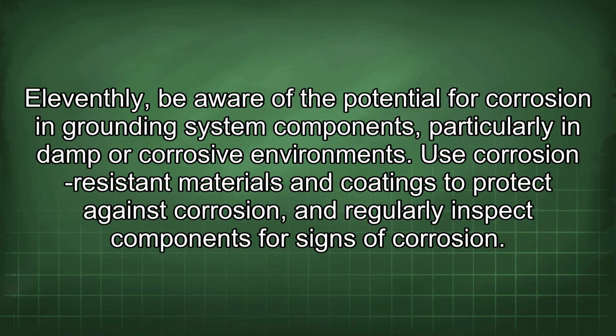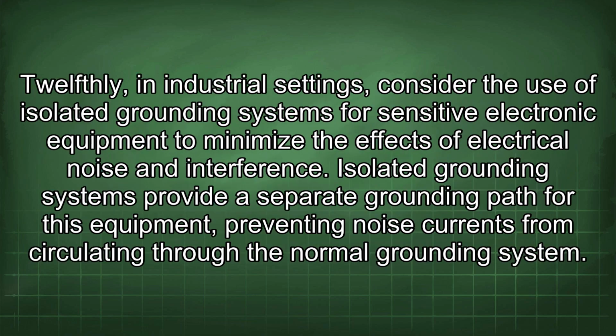11thly, be aware of the potential for corrosion in grounding system components, particularly in damp or corrosive environments. Use corrosion-resistant materials and coatings to protect against corrosion, and regularly inspect components for signs of corrosion. 12thly, in industrial settings, consider the use of isolated grounding systems for sensitive electronic equipment to minimize the effects of electrical noise and interference. Isolated grounding systems provide a separate grounding path for this equipment, preventing noise currents from circulating through the normal grounding system.